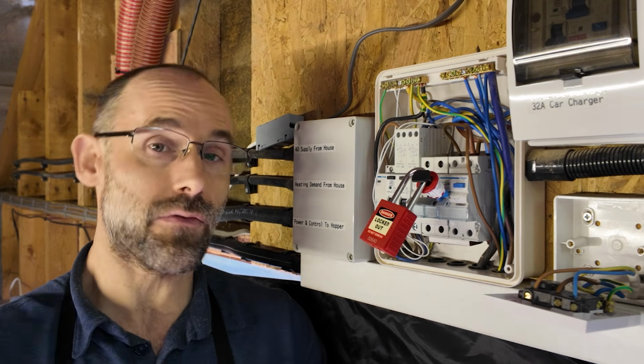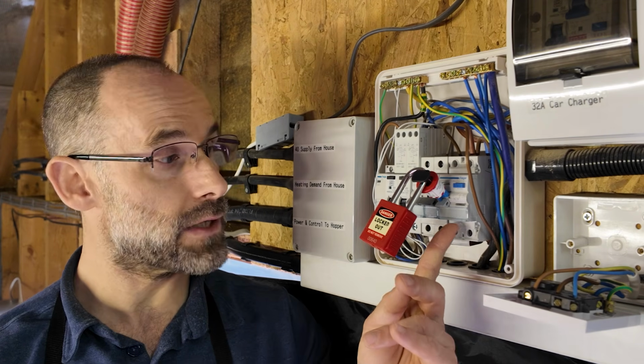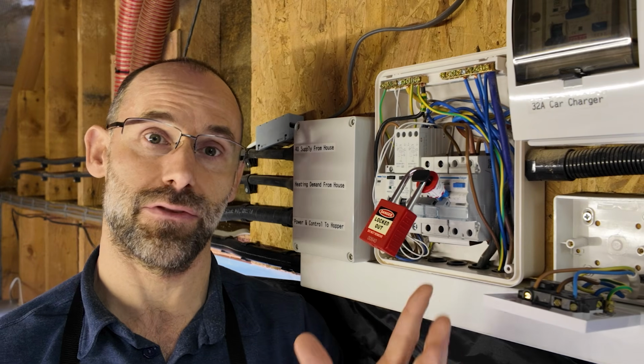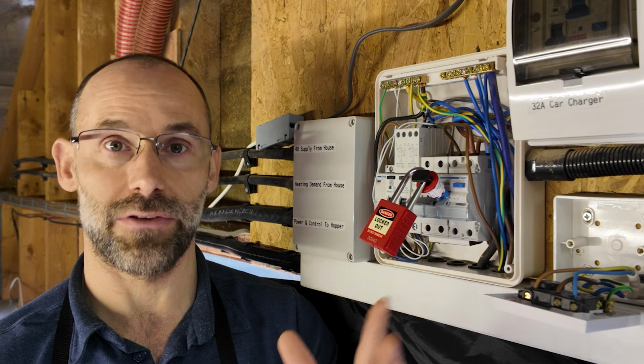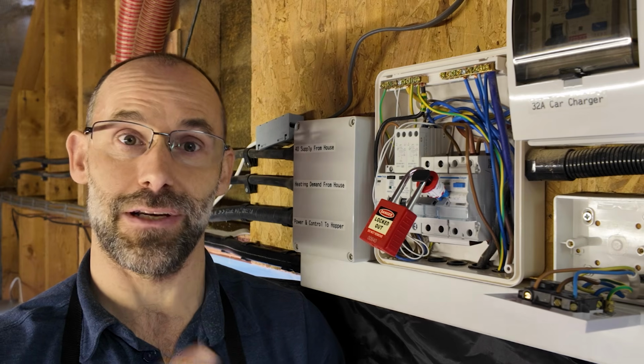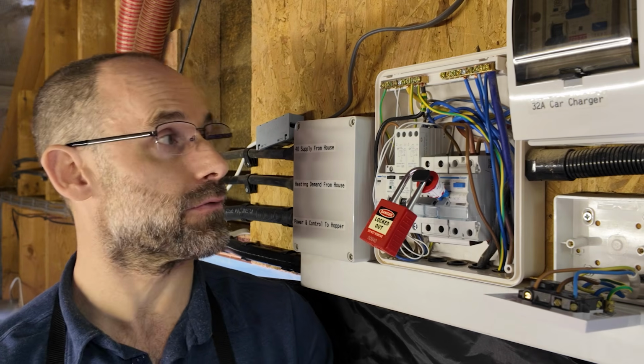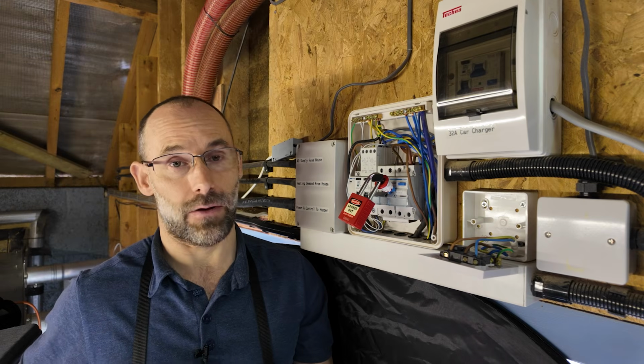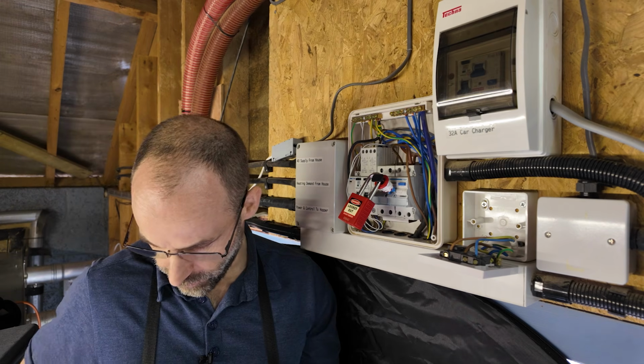Because if the resistance of that loop is too high, there's no way you can get enough current through your GFCI, your ground fault circuit interrupter, or your RCD, residual current device, for it to actually trip. This one needs 30 milliamps to trip. So we're going to check that now. All right. Now I'm just going to show you how that gets checked.